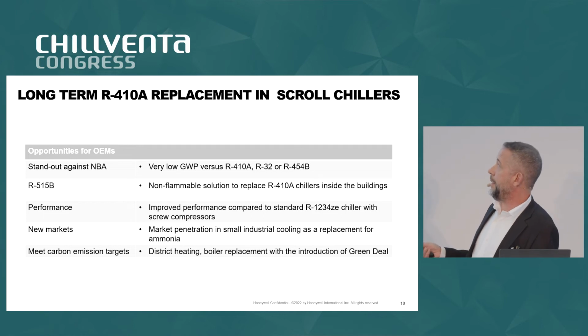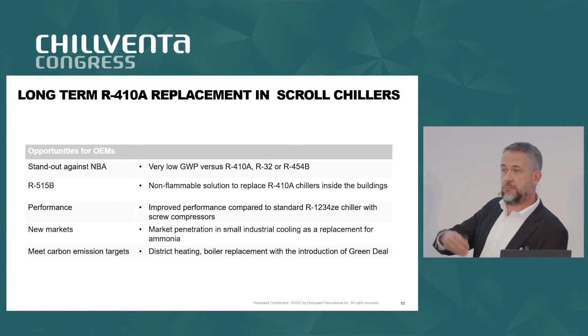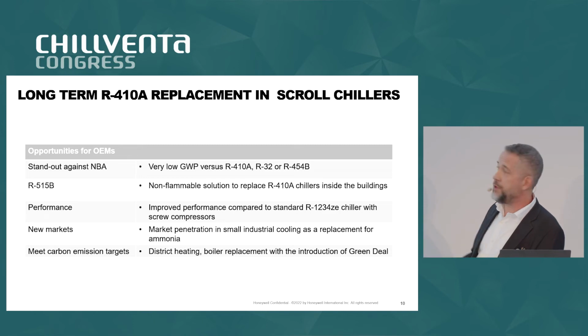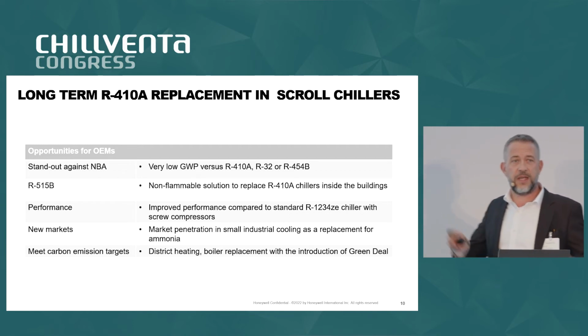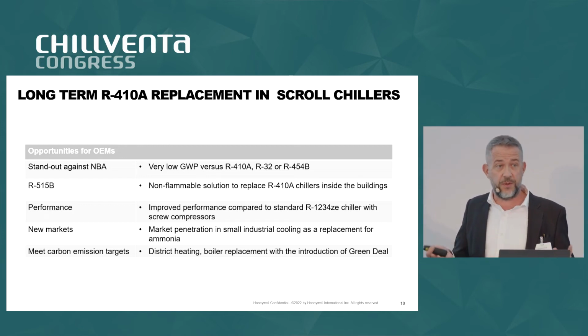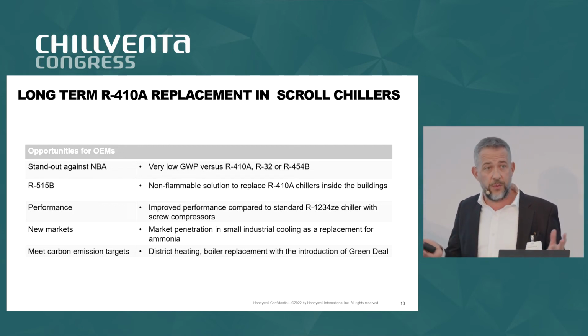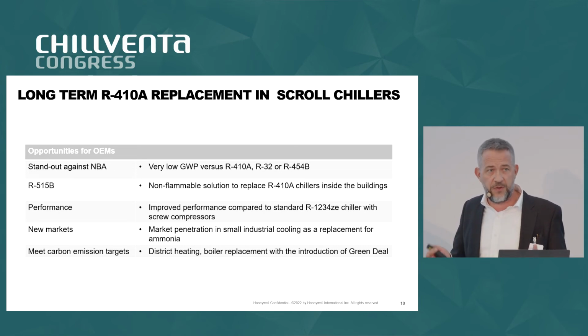Against the next best alternative, which is 410A and the interim solutions, there's obviously the very low GWP, and efficiency as I mentioned. It's 515B - I'm insisting on this - and it has the beauty of being non-flammable. So in many markets, in the US for instance where A2L is not always easy to implement yet, you can already use the same chillers with the same efficiencies, same operating envelope, same water temperatures.